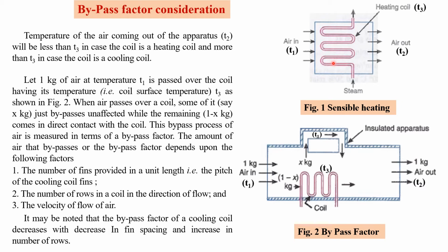We have seen in the previous slide, while looking at the actual pictures of the heating or cooling coil, that the tubes are at a finite distance. Each tube is separated from the other by a definite amount, and they also have fins in between them. So when this unsaturated moist air flows over the tubes carrying steam at high temperature, the air gets heated up. Because the walls of the tubes are impervious, there is no mixing of the air molecules with either the steam or the hot water flowing through the tube. So the moisture content of the air does not change, it remains as it is, only its dry bulb temperature changes.